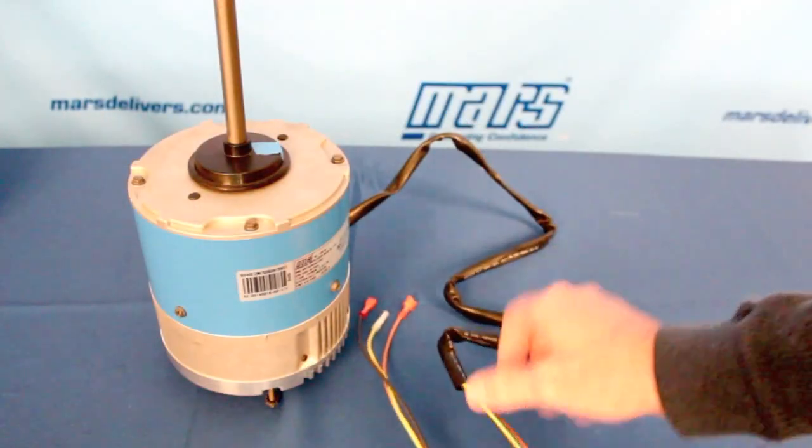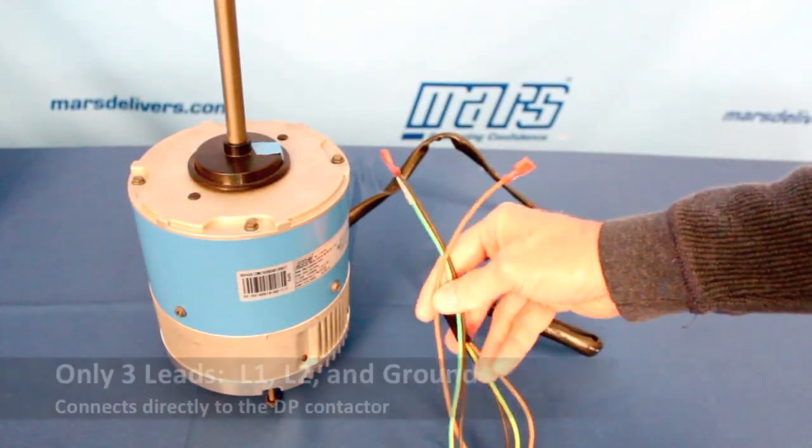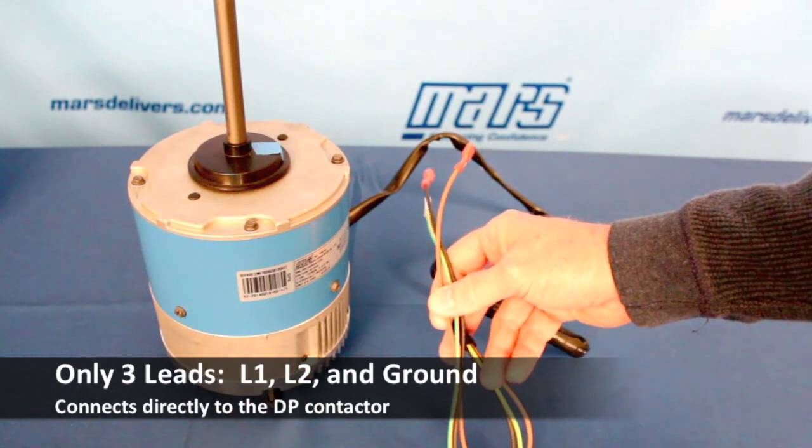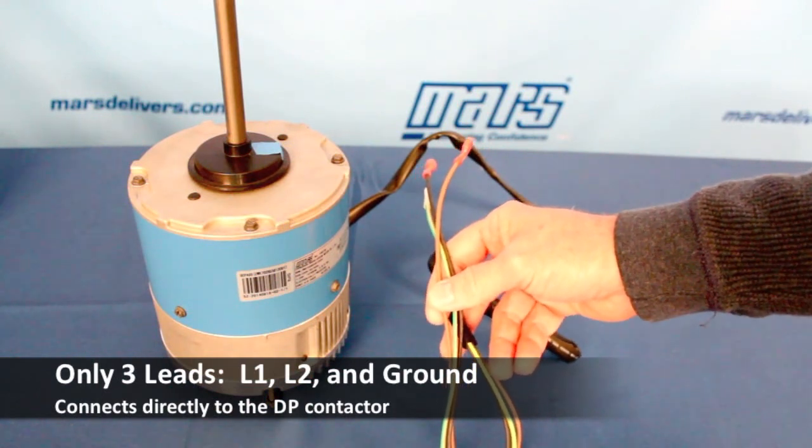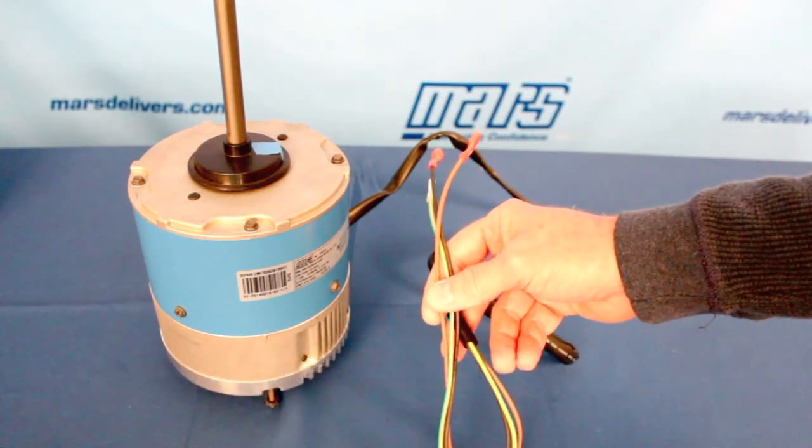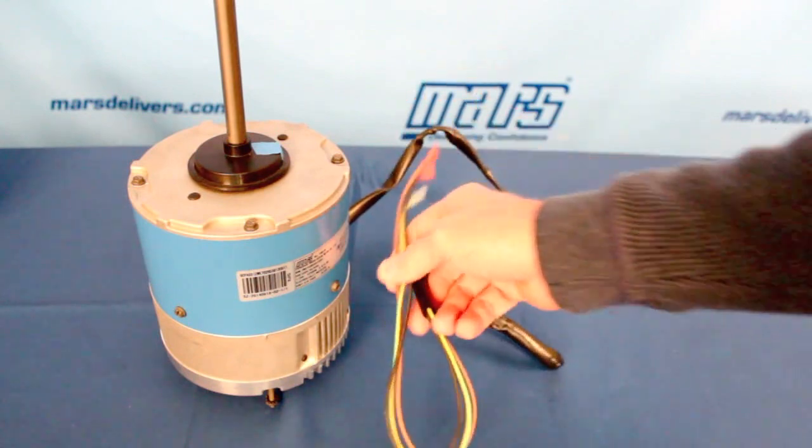When you open the box, you'll notice the motor has a three lead harness: L1, L2, and a ground. This motor connects directly to the contactor. There is no capacitor because this is an ECM motor. It's very easy to install.